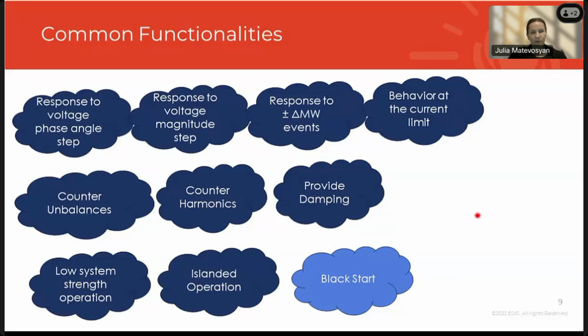Black start, I have it separately in a different color, and I would like to stress this. We always try to stress this difference: not all grid forming are black start capable, but to be a black start unit, you need to be grid forming. And so grid forming inverter-based resources have advantages even without being black start capable, and they can provide improved stability of the system when the system is all together and connected. But then you can also design inverter-based resources to be black start capable, but they need to be grid forming for that.